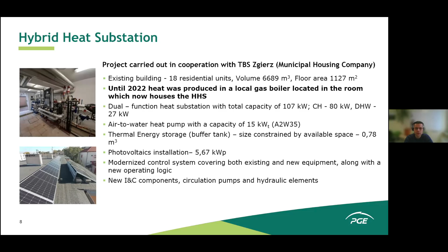This installation was handed over in November 2023, and results for 1 year of operation are presented here. As you can see, almost 40% of all heat was supplied from the heat pump, so the remaining 60% was from the district heating network, and 25% of all heat was delivered from renewable energy sources—meaning the heat pump when it was taking electricity from the photovoltaic.